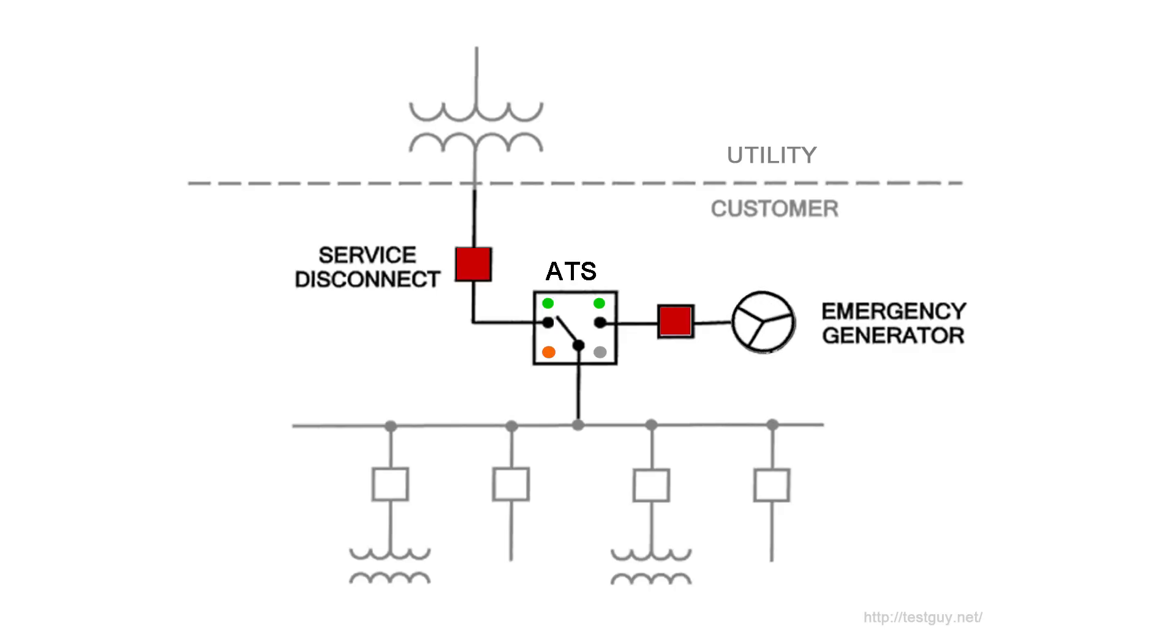Step 6. The delay engine stop timer will begin its timing cycle. The generator runs unloaded for the duration of this timing cycle. When the timer completes its timing cycle, the generator will stop. The source 2 available lamp goes off. A minimum time delay of 5 minutes should be provided for unloaded running of the emergency power system prior to shutdown. This allows the engine to cool down. The minimum 5 minute delay is not required on small air-cooled prime movers 15 kW or less.